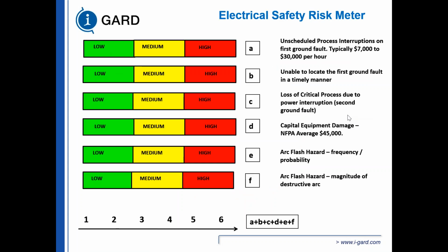So we came up with an electrical safety risk meter. And so we've assigned numbers of 1 to 6 for different types of systems. For example, in column A, or box A, unscheduled process interruptions on first ground fault, typically $7,000 to $30,000 per hour for an outage. Now, $7,000 to $30,000 is not a lot of money. So there's a risk meter associated with that, the ability to locate the fault or the first fault in a timely manner. We'll assign a number from 1 to 6 in there, and we're going to use this to measure different types of grounding systems.